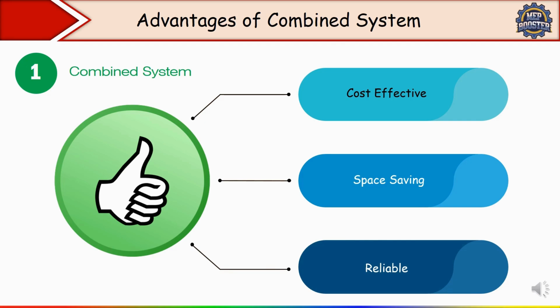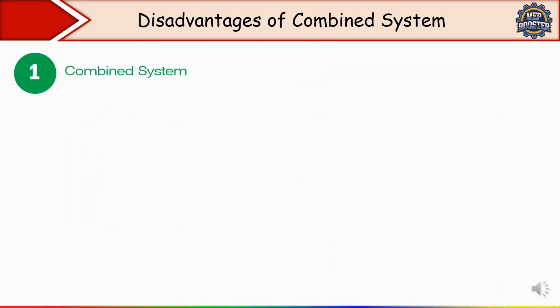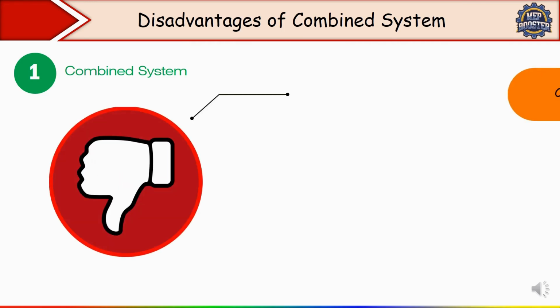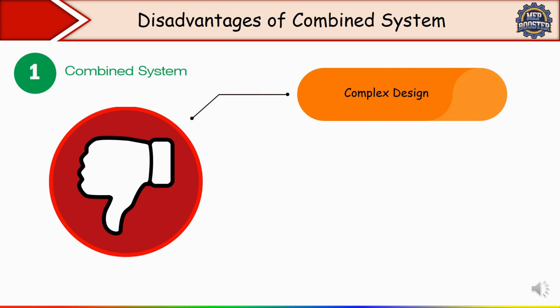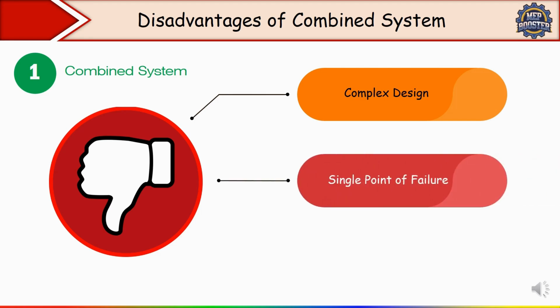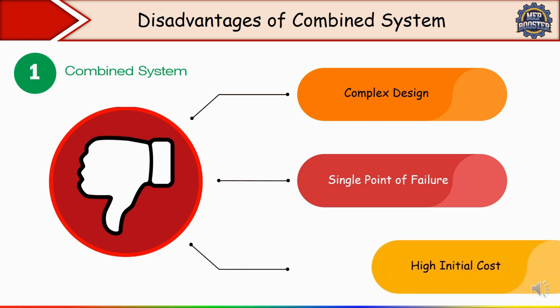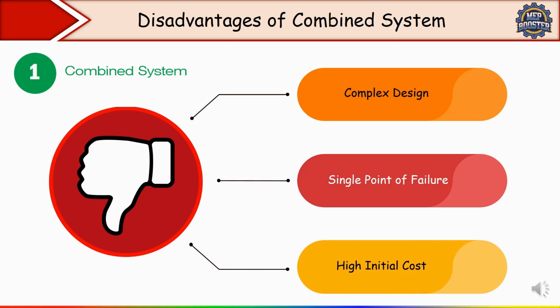Clear? Now we'll see the disadvantages of combined system. The first one is complex design. Yes, because this combined system requires detailed hydraulic calculation. So it is a complex design. Second, single point of failure. Here a pump failure affects both systems. And then high initial cost. Yes, because it is more expensive than a standalone system. So initial cost is high. Clear? So these are the disadvantages of combined system.